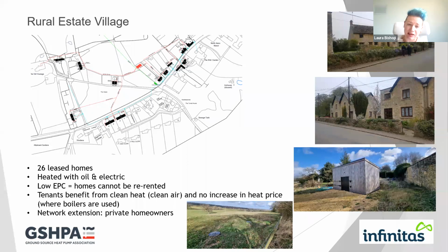That's all you can see after the field has regrown. You don't actually get anything left over apart from the black caps you can see there, which is the manifold covers. That is then delivering heating at 55 degrees C into a heat network - you can see that in the red lines on the picture on the left-hand side. So brand new preinsulated pipe, taking 3 legs to different parts of the village.